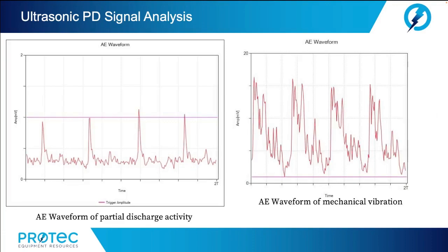Now, it is possible that core vibration in a transformer can produce an ultrasonic signal which is very similar to partial discharge. We can use several strategies to determine if the signals are PD or only vibration. We can compare the width of the peaks to the height of the peak. The PD signals have a narrow width and a tall peak. The vibration signals have a wider base and a wider peak, which may split into multiple peaks.